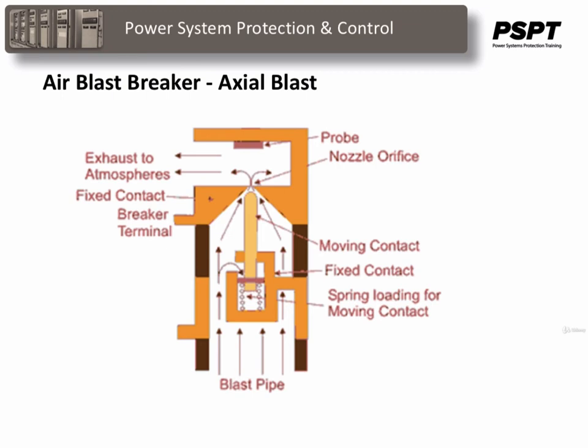The air pressure will counter the spring pressure and deform the spring, hence the moving contact is withdrawn from the fixed contact and the nozzle hole becomes open. At the same time, the high pressure air starts flowing along the arc through the fixed contact nozzle orifice. This axial flow of air along the arc through the nozzle orifice will make the arc lengthen and cool. Hence, arc voltages become much higher than system voltages. That means system voltage is insufficient to sustain the arc. Consequently, the arc is quenched.